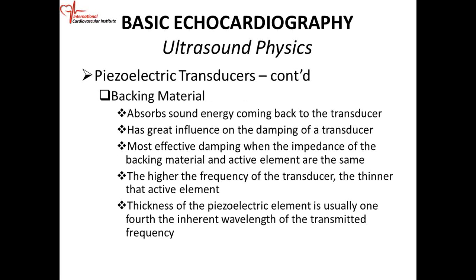The backing material absorbs the sound energy coming back to the transducer. It has a great influence on the damping of the transducer. It's most effective in damping when the impedance of the backing material and active elements are the same. The higher the frequency of the transducer, the thinner the active element. And the thickness of the piezoelectric element is usually 1/4 of the inherent wavelength. So basically, you just have to have an idea what these layers look like and where they are located.